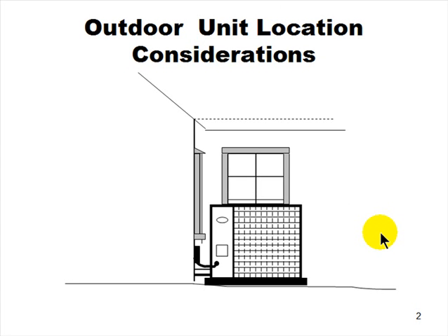Outdoor unit location considerations. Now, what we're going to talk about here applies to air conditioning condensers as well, but it's particularly important for heat pumps. Proper air circulation. Clearances. Don't do this, especially if the back of this is the service panel. Because there's no way in the world you're going to get in there and work on a compressor. You're going to end up taking this whole frame apart because you've got to go in from the top. Use your head. Give yourself room to work.